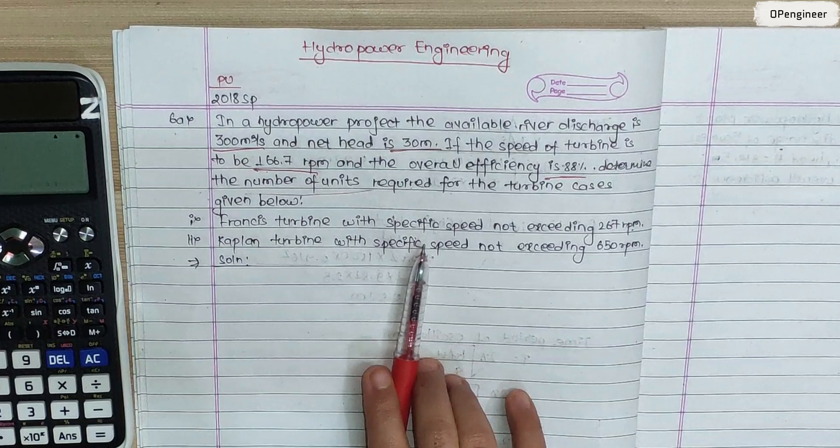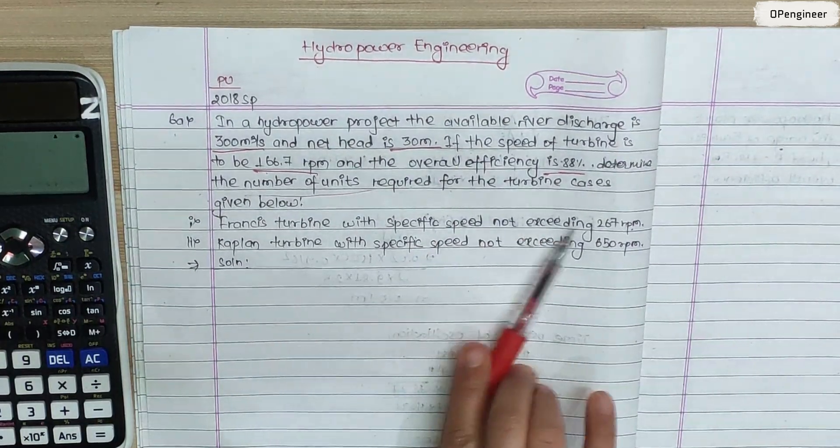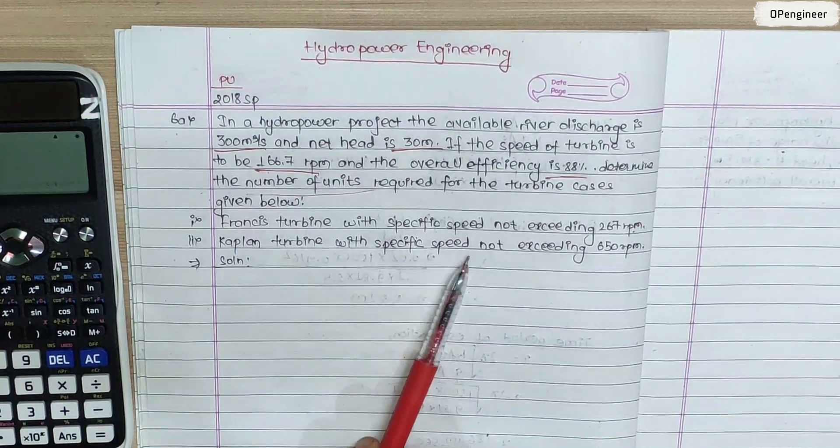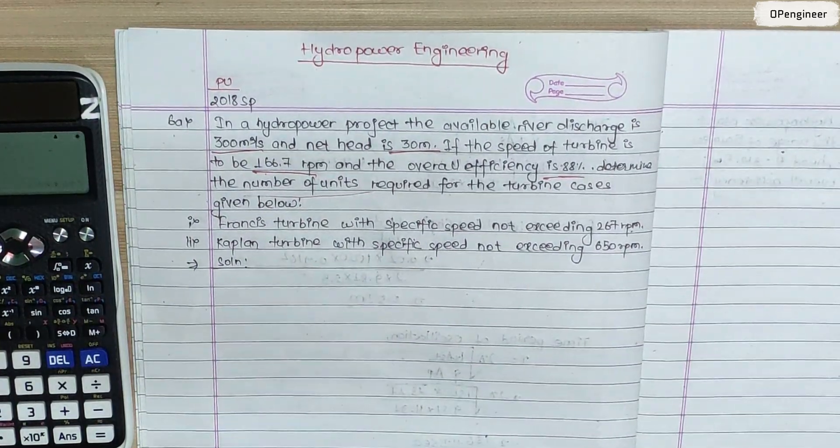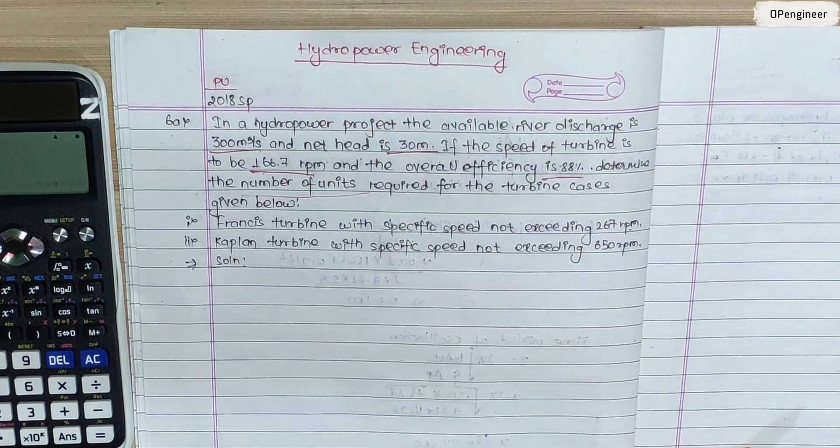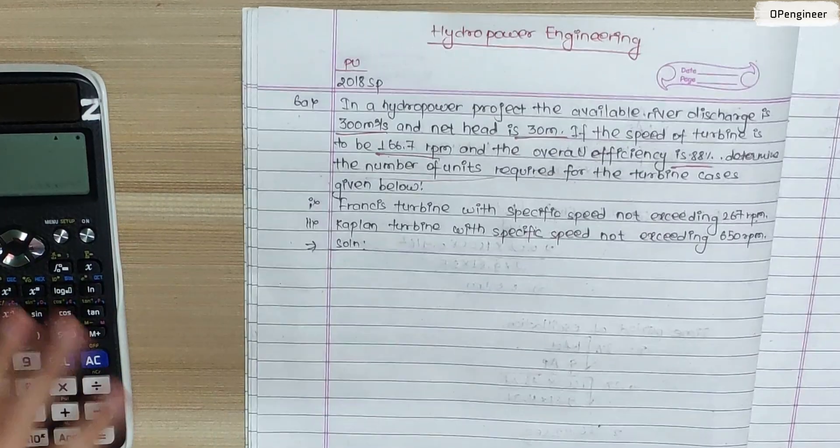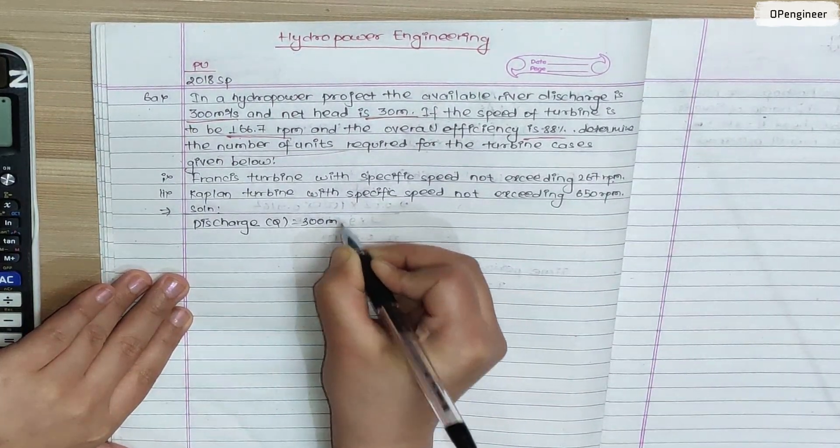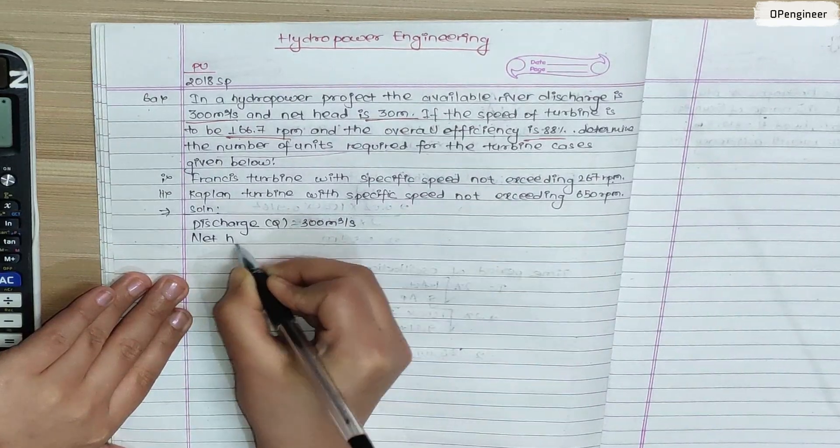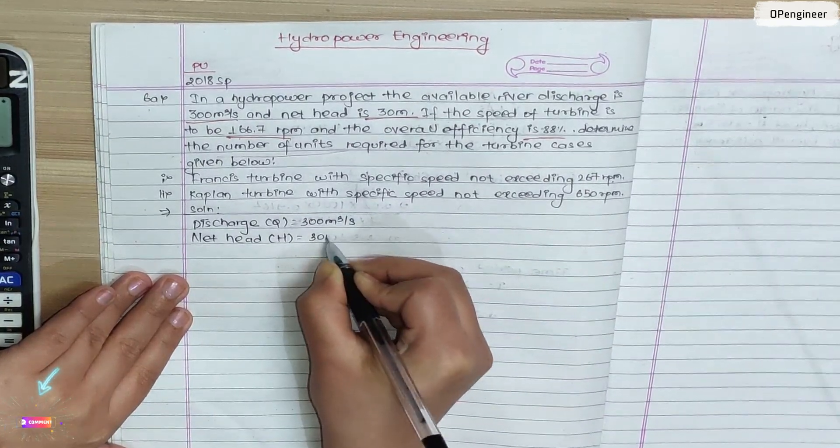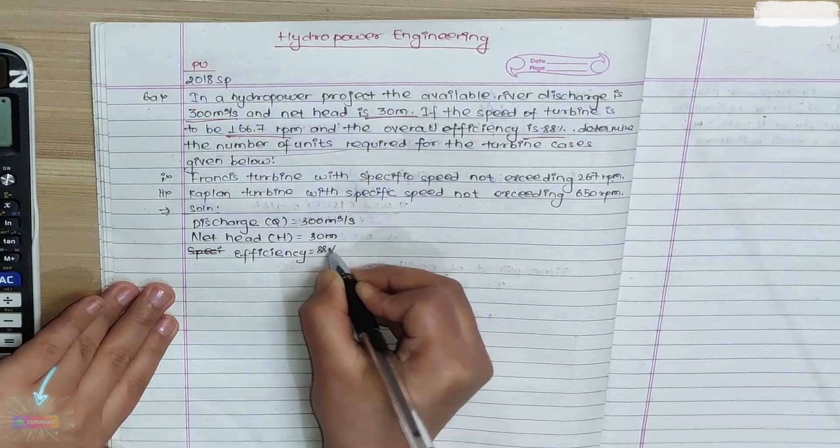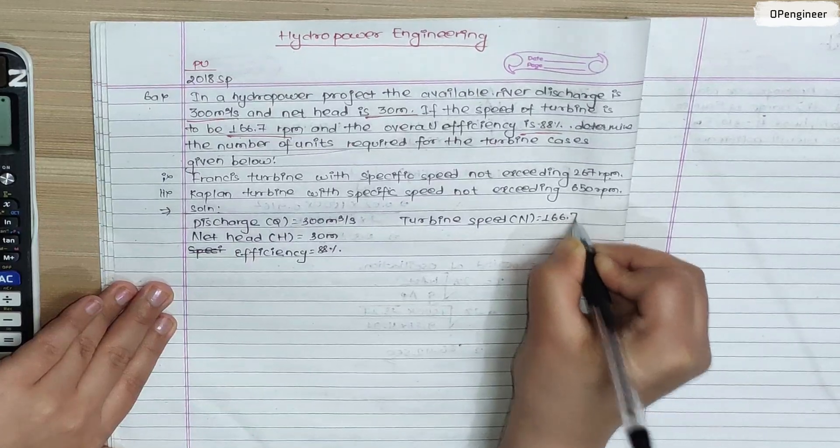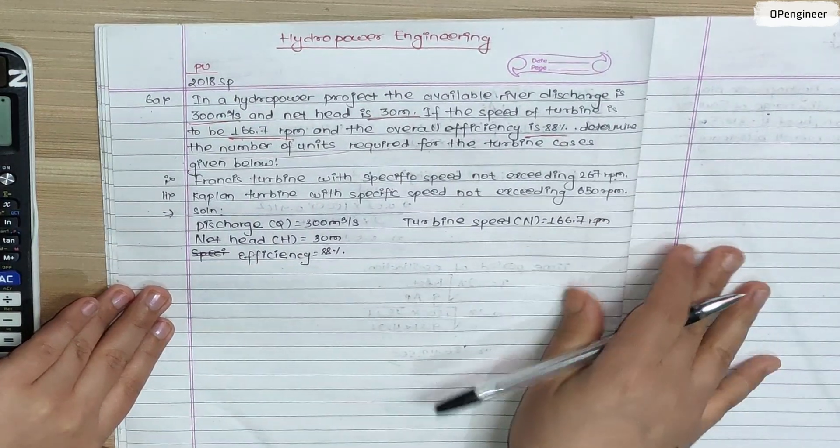Turbine cases: Francis turbine with specific speed not exceeding 267 rpm, Kaplan turbine with specific speed not exceeding 650 rpm. So at the beginning of the question, let me give you the given data. Discharge Q = 300 cubic meters per second, net head H = 30 meters, overall efficiency η = 88%, turbine speed N = 166.7 rpm.